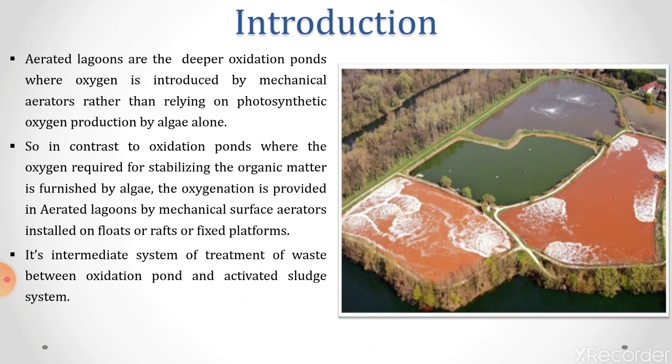Externally the oxygen is provided, as the aerated lagoons are deeper than the oxidation pond, or rather we can say these are the deeper oxidation ponds. So, in contrast to the oxidation pond, where the oxygen required for stabilizing the organic matter is furnished by the algae, the oxygenation is provided in the aerated lagoon by the mechanical surface aerator installed on the float or raft or fixed platforms.